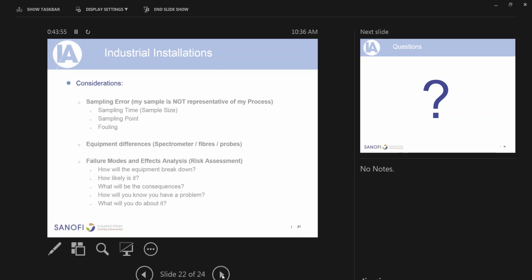There are three things to think about if you're putting a Raman spectrometer into a production plant. The first is sampling error. What this means statistically is that my sample is not representative of my process. What I'm looking at is not the truth of what's going on in my process. I have faulty information, and so I'm reacting to the wrong things. And the reasons this happens are that our sample size is too small or irrelevant, our sampling point is irrelevant if it's not representative of the whole, or our probe is fouled and it's just measuring something else entirely.